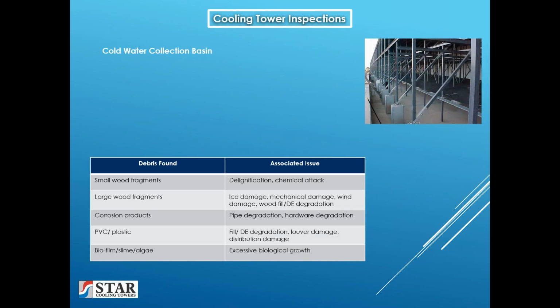Start with the cold water collection basin. The basin has two important functions. One is the collection of the water to be pumped back to the heat source, and it's the primary foundation for the cooling tower structure. A visual inspection of the masonry for cracks, leaching of calcium, and spalling of any of the masonry materials. The base anchors and anchor bolts should be inspected for corrosion and cracks or any other problems.